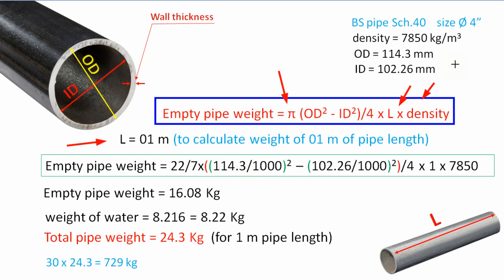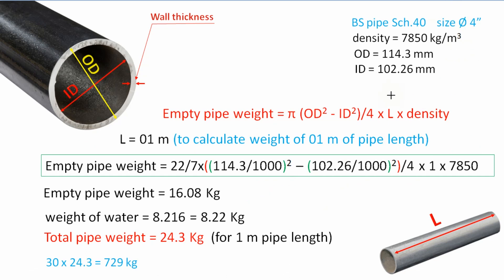For the sample calculation, we assume pipe length equal to 1 meter. We apply the values: empty pipe weight = (22/7) × (114.3/1000)² — converting outside diameter from millimeters to meters by dividing by 1000 — minus inside diameter squared, divided by 4, into pipe length of 1 meter, then multiplied by pipe density 7850. The empty pipe weight is equal to 16.08 kilograms. The weight of water inside the pipe we already calculated as 8.216 kilograms (which we can also write as 8.22 kg). Adding empty pipe weight and weight of water, the total pipe weight is equal to 24.3 kilograms.